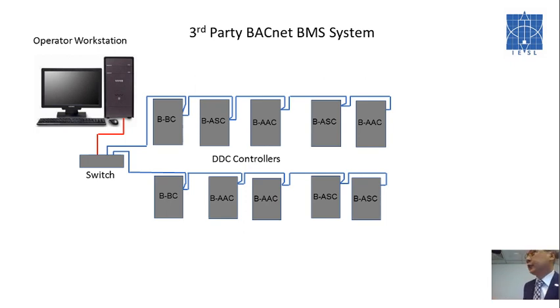So for a BACnet system, why do we need BACnet compared to a proprietary system? Because we want to protect the end user. If you have a proprietary system, you can't go to anyone else but that particular brand. With a BACnet system, 3 years, 10 years down the road, if the building owner doesn't like the service or quality of the products, he has the choice to change.